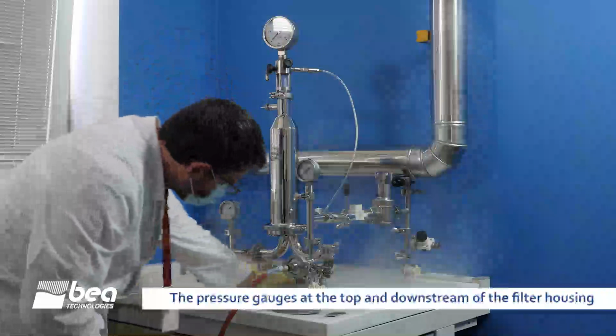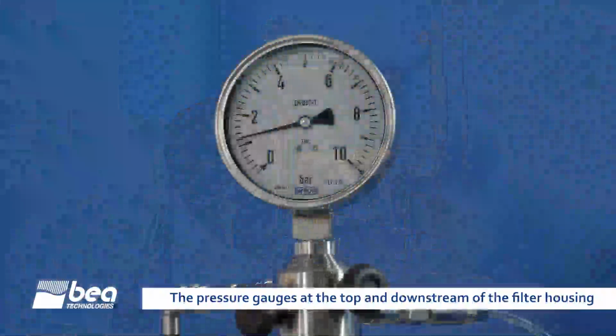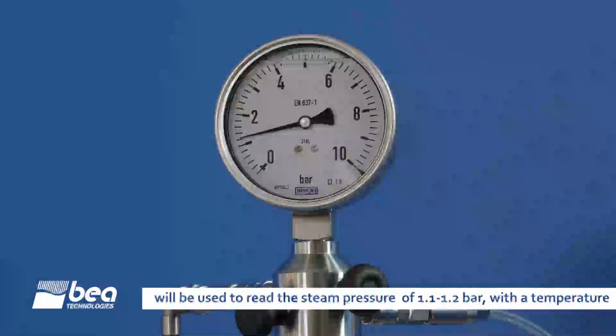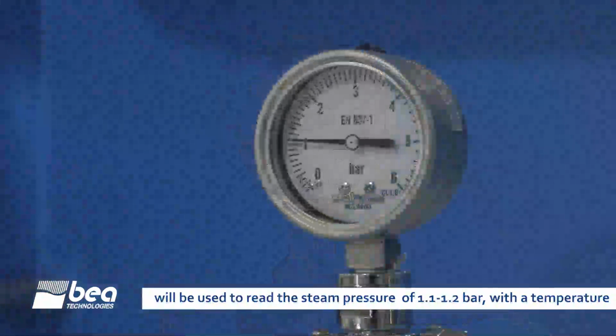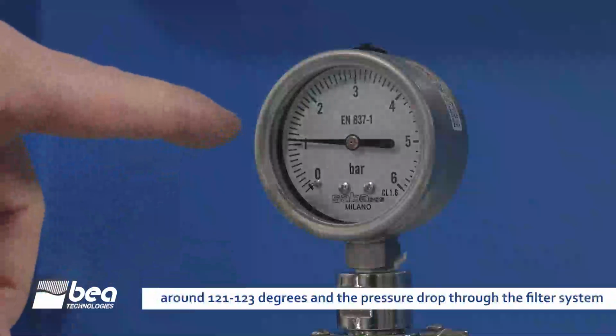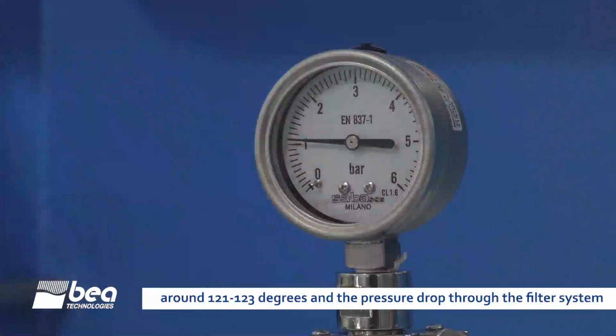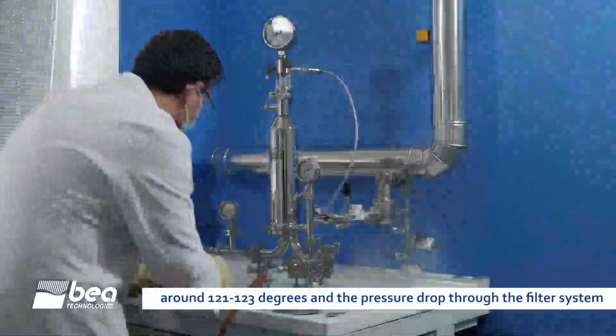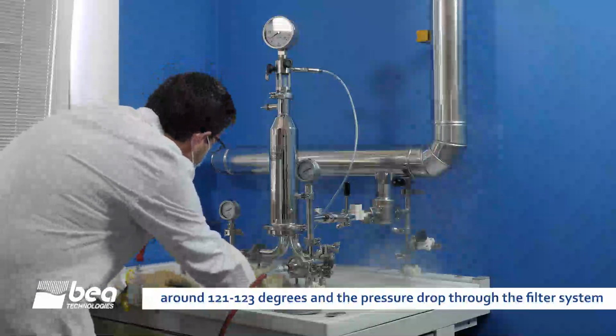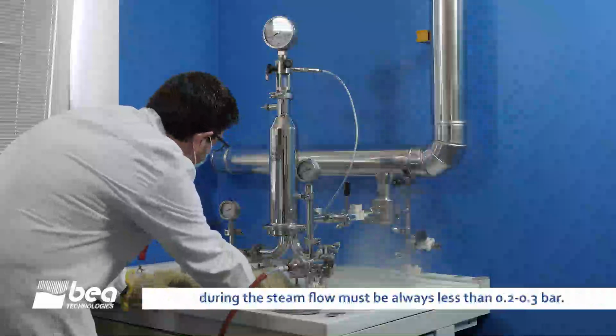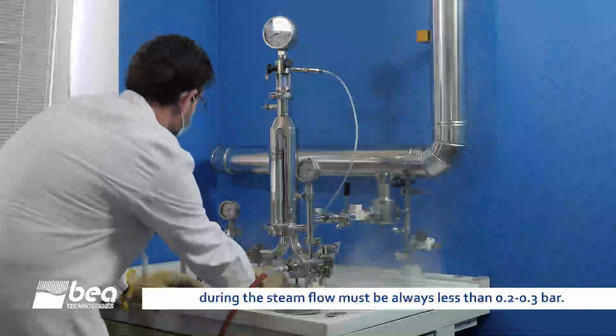The pressure gauges at the top and downstream of the filter housing will be used to read the steam pressure of 1.1 to 1.2 bar, with a temperature around 121 to 123 degrees. And the pressure drop through the filter system during the steam flow will always be less than 0.2 to 0.3 bar.